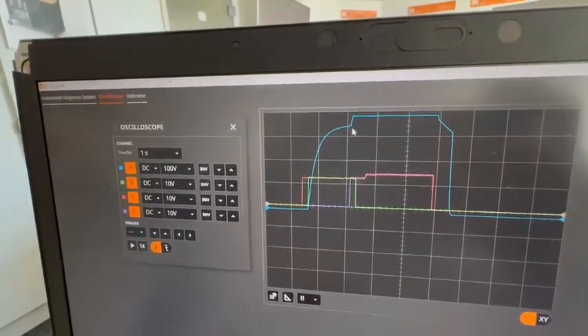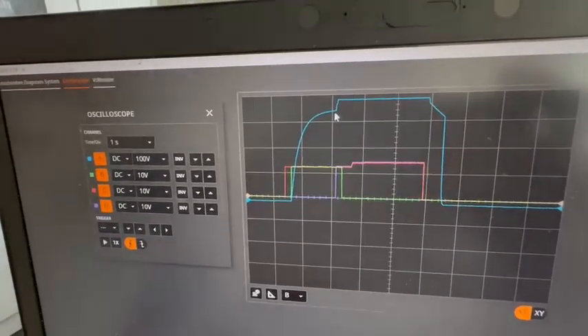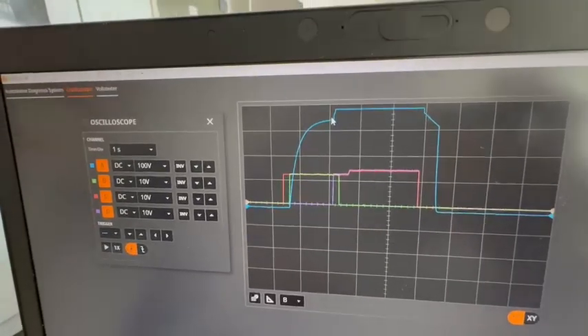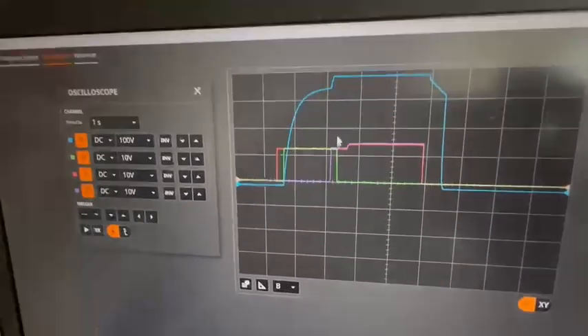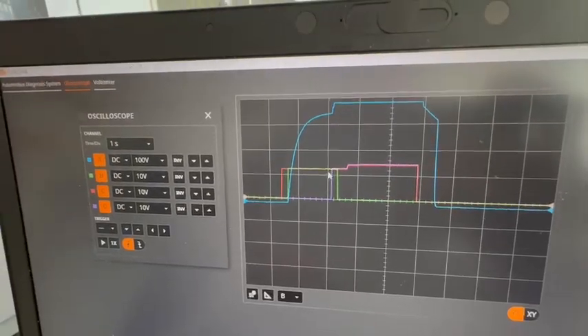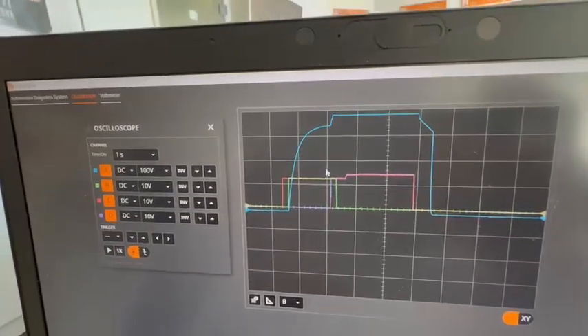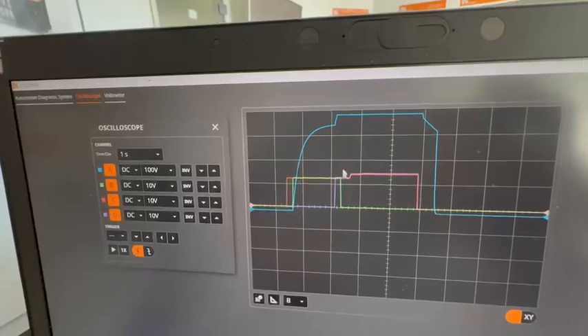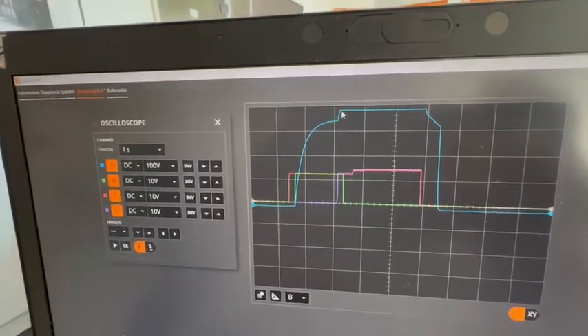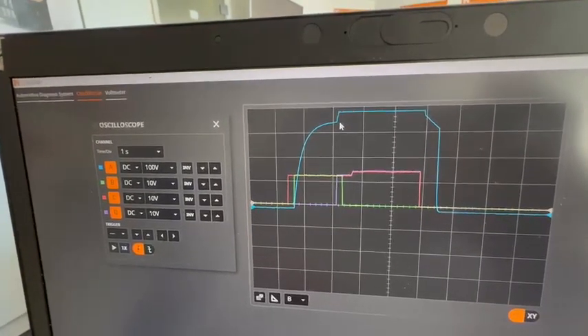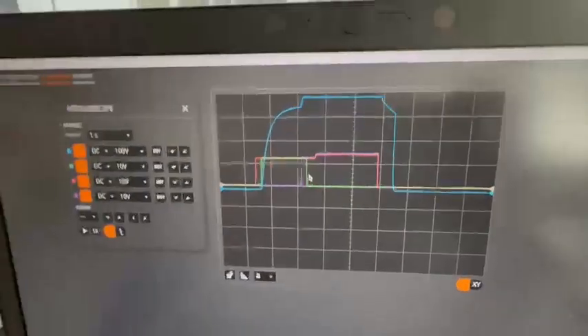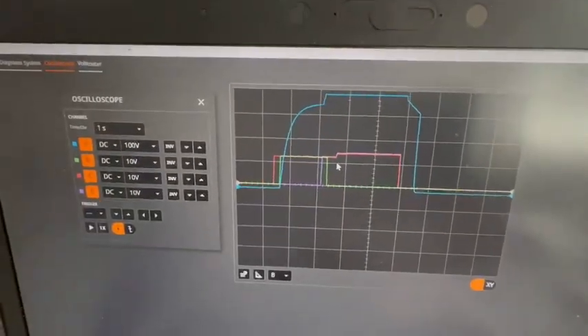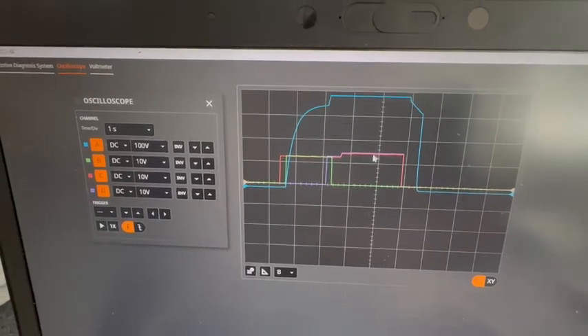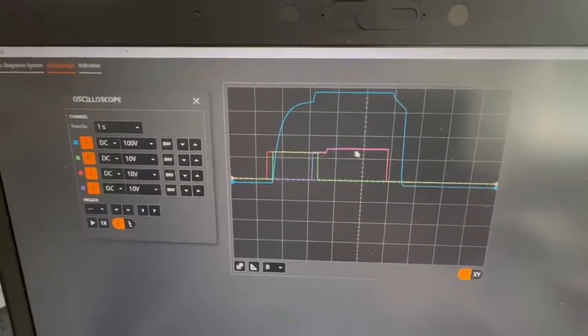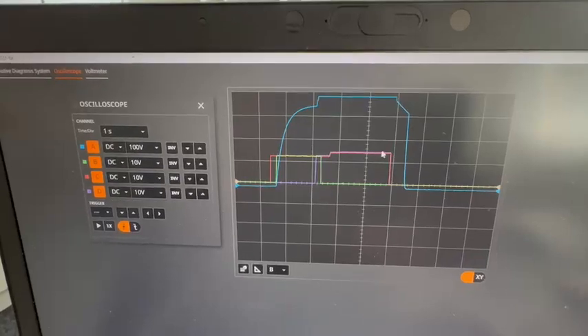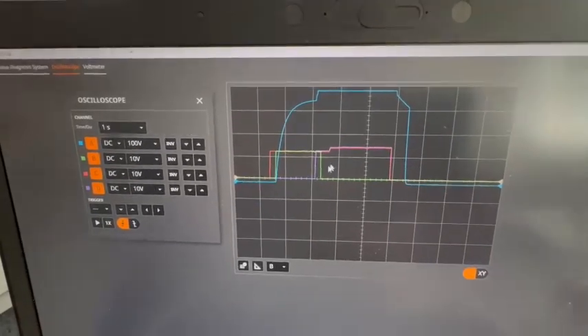Once we get to this point where, say, 90% of the voltage is achieved, the BMS says okay, everything's fine, and now I can turn on the main contactor. So the main contactor comes on here, we get our full voltage coming up to that point, so up to 400 volts. The pre-charge can then switch off and say, all right, my job's done. And then we're just left with positive and negative relays closed here until switch off.